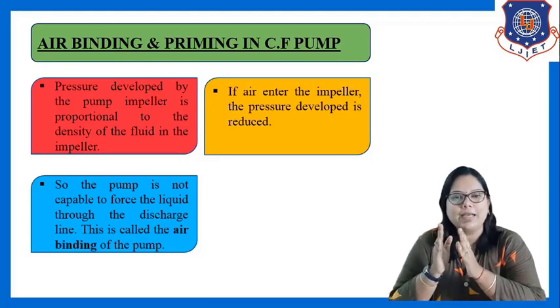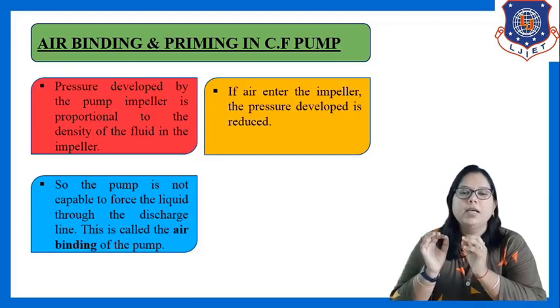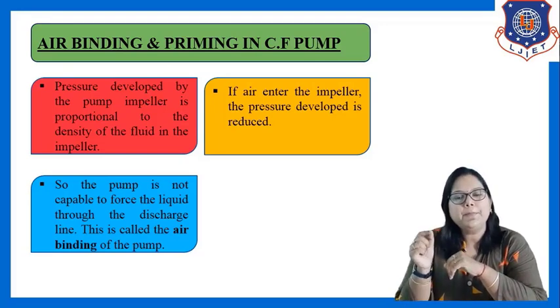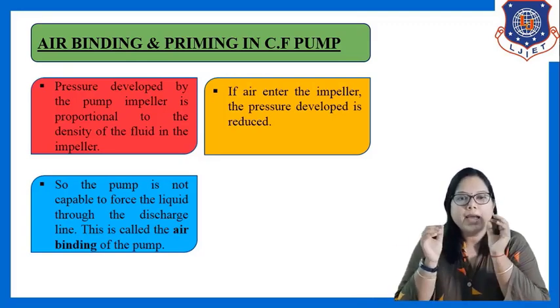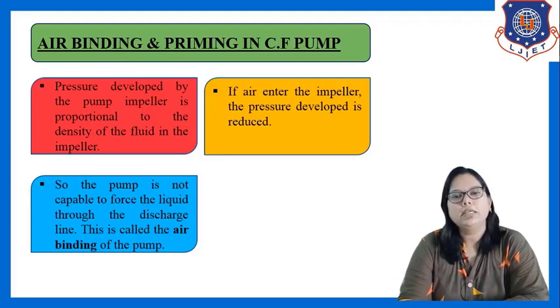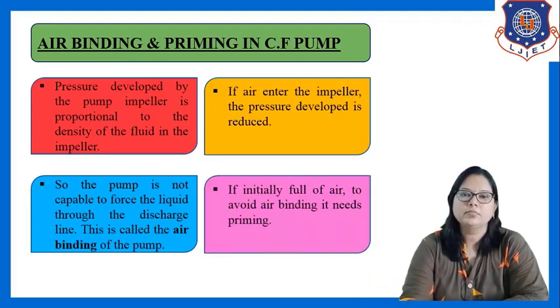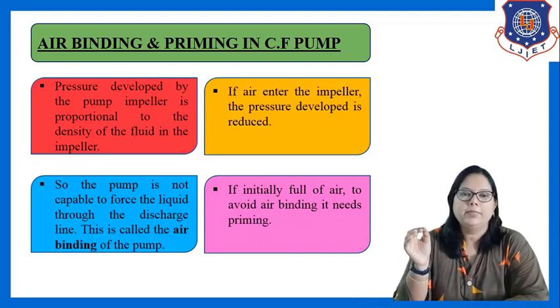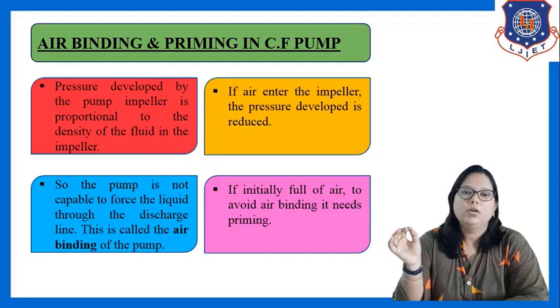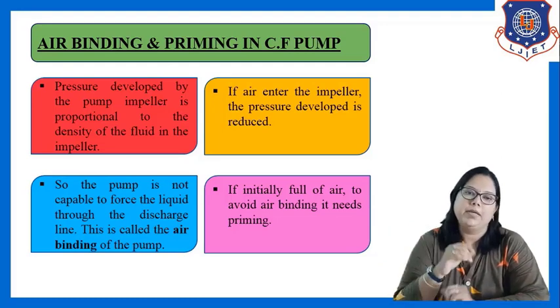So in general I can say that when air enters the pump impeller, there is reduction of pressure in the pump impeller, and due to that the pump is not capable of transferring liquid from the suction line to the discharge line, and that condition is known as air binding of the pump. At that time, the pump is not capable of transferring liquid. To resolve this condition of air binding, the pump needs priming.